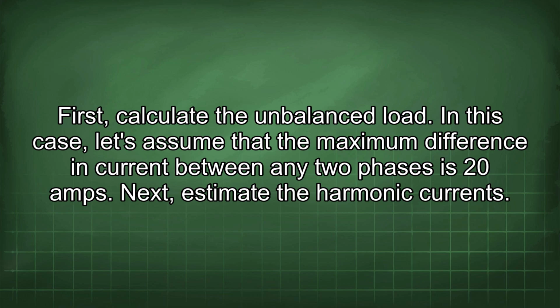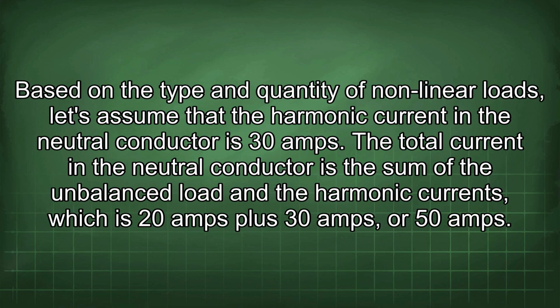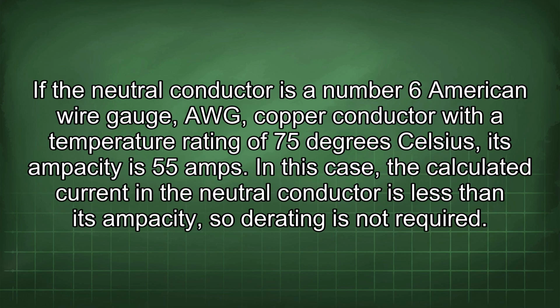In this case, let's assume that the maximum difference in current between any two phases is 20 amps. Next, estimate the harmonic currents. Based on the type and quantity of nonlinear loads, let's assume that the harmonic current in the neutral conductor is 30 amps. The total current in the neutral conductor is the sum of the unbalanced load and the harmonic currents, which is 20 amps plus 30 amps, or 50 amps. If the neutral conductor is a number 6 American wire gauge (AWG) copper conductor with a temperature rating of 75 degrees Celsius, its ampacity is 55 amps. In this case, the calculated current in the neutral conductor is less than its ampacity, so derating is not required.